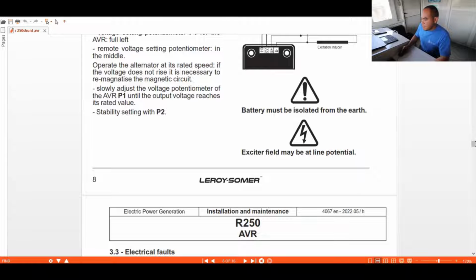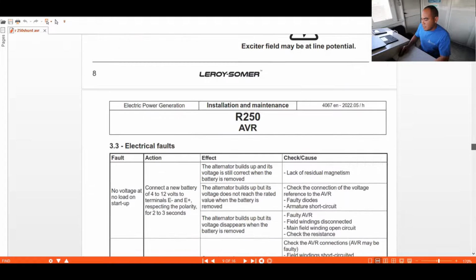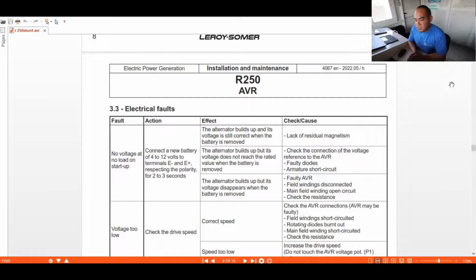Now, let's talk about the fault findings for our AVR. This functionality is more important. For example, your AVR has no voltage at no-load startup. What you have to do is check the causes. If there is no voltage at no load during startup, it means there is no residual magnetism. So here are your actions: you can connect a battery of 4 to 12 VDC to the terminals E negative and E plus, respecting the polarity, for 2 to 3 seconds. So follow the polarity when you are doing this excitation.